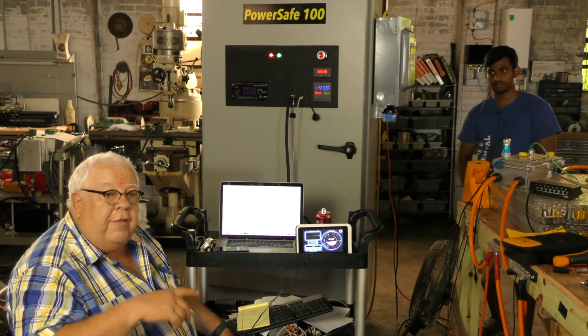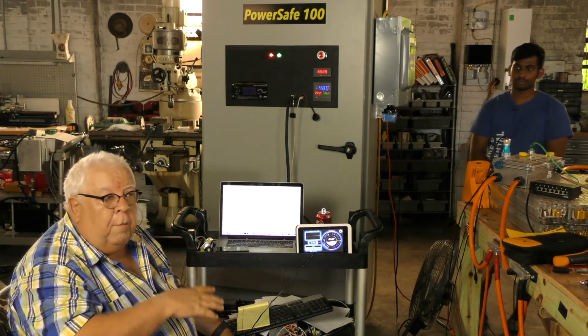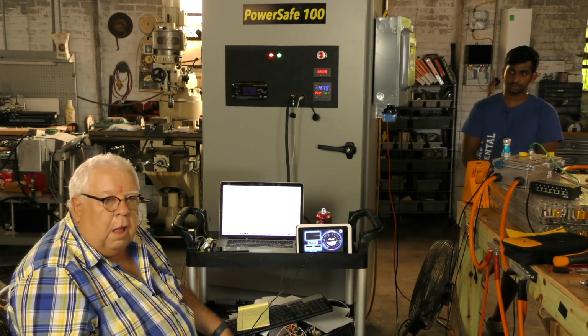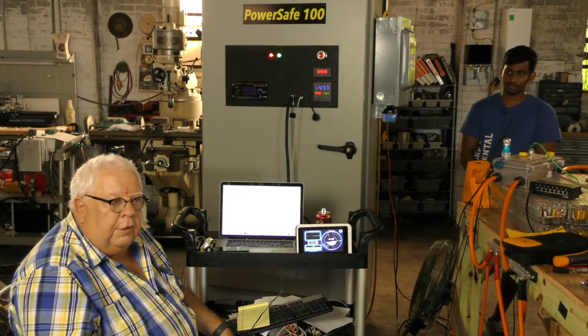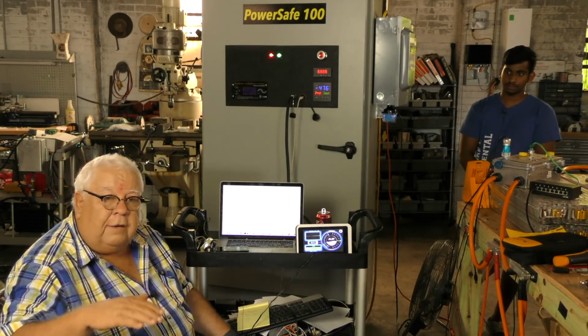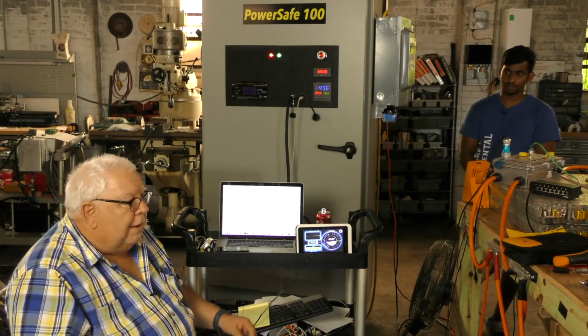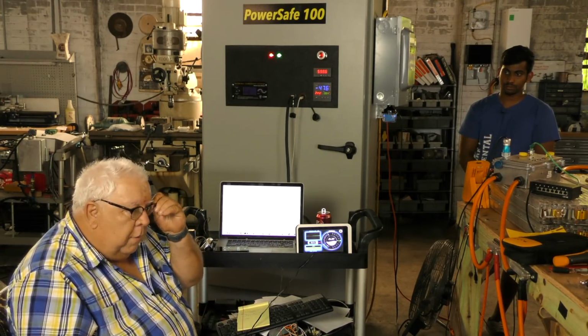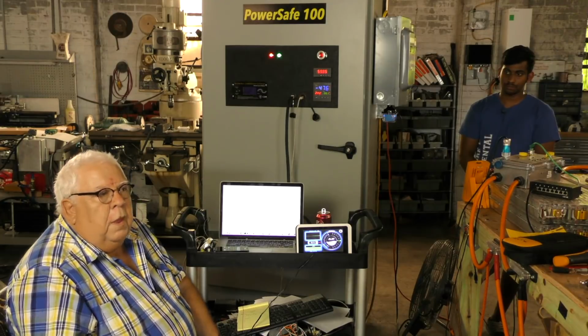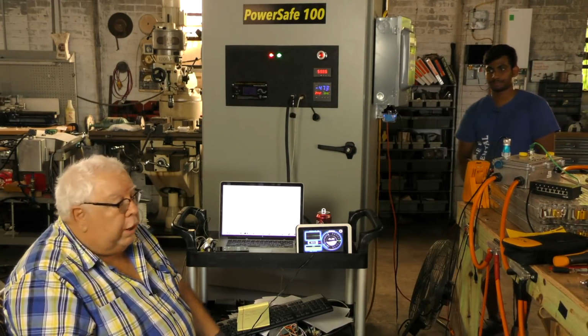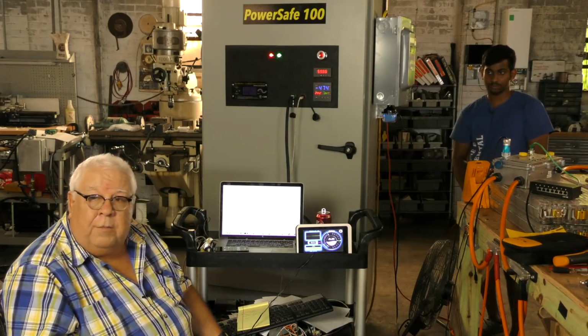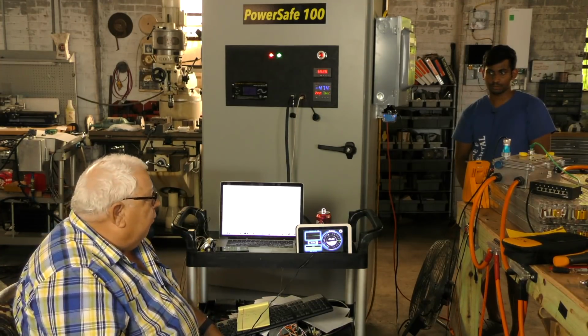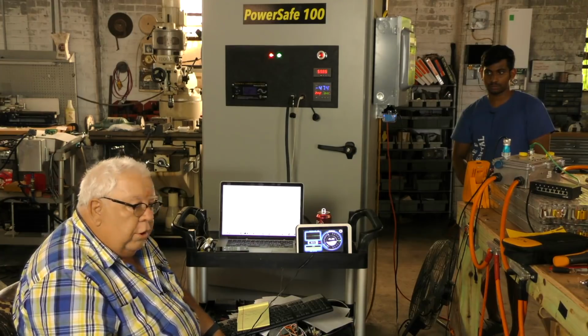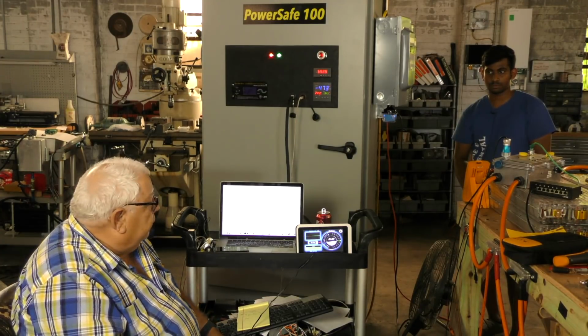So you'll do that in the afternoon. You'll charge all morning till say 2 or 3 o'clock until you reach full on your batteries, and then it'll sit there and cycle on and off, slowly on a 20 or 30 minute cycle, and do that until the sun goes down, then it'll be ready to charge when the sun comes up in the morning, and you operate off the batteries at night. But you go into the evening with a mostly full pack, depending on where you set your cutoff and resume.